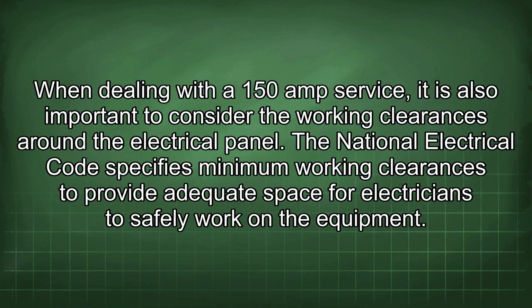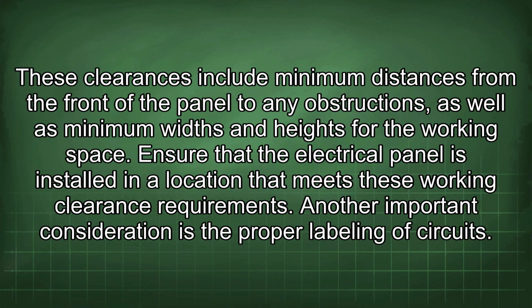When dealing with a 150 amp service, it is also important to consider the working clearances around the electrical panel. The National Electrical Code specifies minimum working clearances to provide adequate space for electricians to safely work on the equipment. These clearances include minimum distances from the front of the panel to any obstructions, as well as minimum widths and heights for the working space. Ensure that the electrical panel is installed in a location that meets these working clearance requirements.